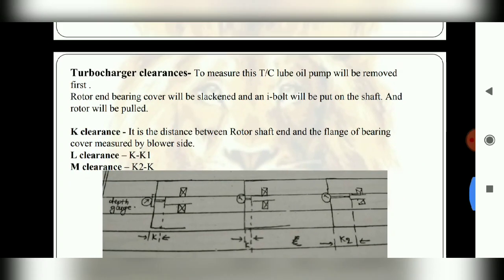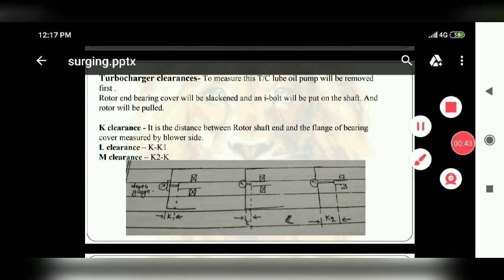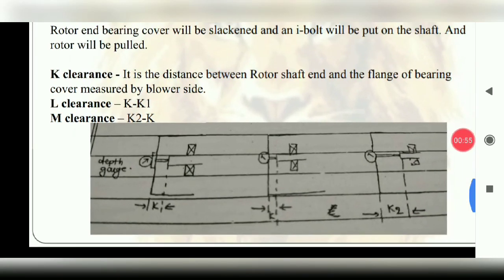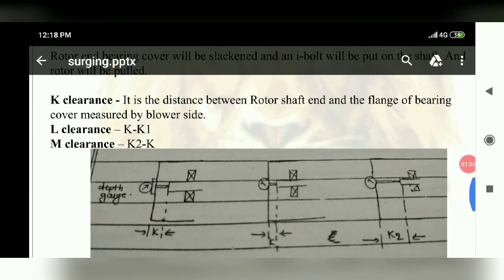If we go further, we will talk about the turbocharger clearances. So basically there are three types of clearances: K clearance, L clearance, and M clearance. Distance between rotor shaft and bearing flange cover. I will show you. This is the rotor shaft and this is the bearing end cover. So this distance will be normally K.